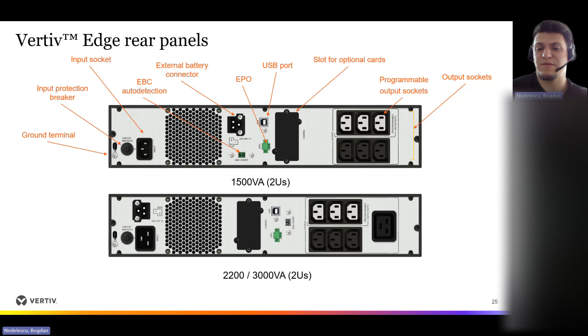And this is how a part number looks like on our UPS solutions, or how our UPS solutions can be identified. As you see, they are very intuitive as every part represents a key element. So if we begin with the first one, we can find the family this UPS is coming from. Here we are talking about the Edge model. Then we have the power load, so here we are talking about a 1.5 kVA version. Then we have the I, which comes from the nominal voltage in Europe, which is 230 volts. Then the installation capability, which is RT, that stands for rack and also tower version. How many units will this UPS occupy in the rack system? This UPS will occupy 2 units. And XL will tell us that external battery cabinets can be connected to this UPS, and we can extend the standard runtime.